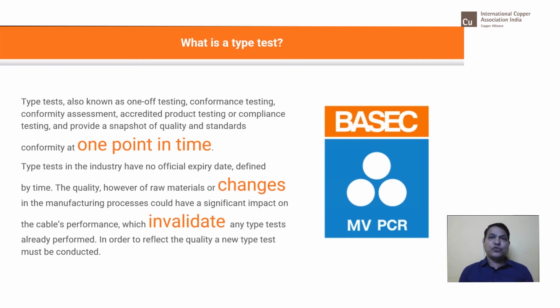However, it is important to note that the raw material or any change in manufacturing process could impact cable performance, which would mean the type test performed would not be relevant in the future. So that is the reason there is no consistent testing to check, unlike product approval. We say type testing is testing on the golden sample. The manufacturer specifically makes one good sample for the type testing. But product approval is totally different, which I'm going to cover in the next slides, which I have made specifically.